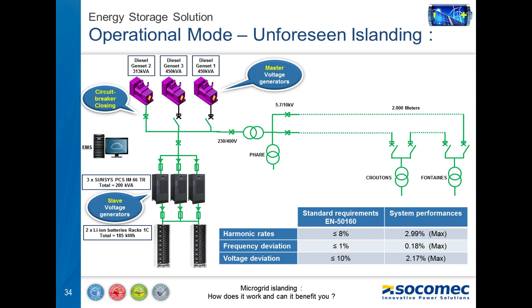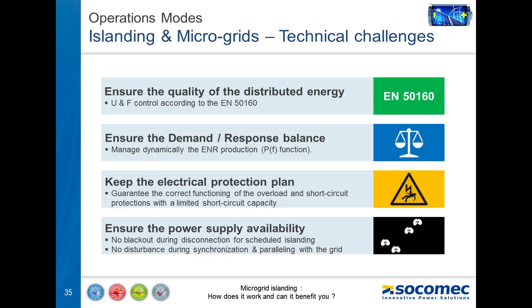Once these three parameters are completely aligned, the controller gives the authorization to close the circuit breaker. This procedure is done without, one more time, any disturbance for the load. These tests were done during the islanding process to check the values in comparison to the standard EN 50160 requirement. As you can see in the table shown in the bottom right corner, the values are far better than the maximum acceptable value. This solution really ensures the microgrid stability.